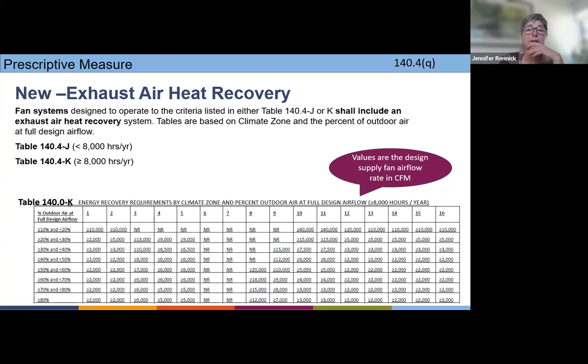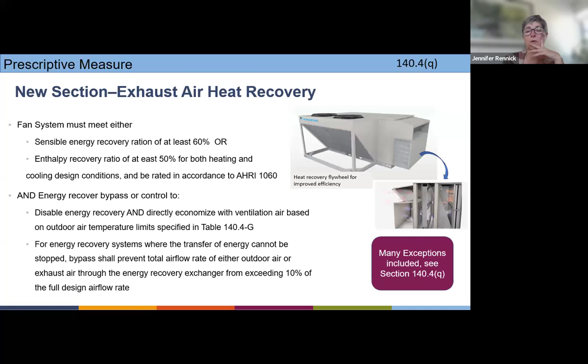And then a lot of the bigger systems we're seeing, they'll just have a large air handler that has a heat recovery flywheel that is going to bring in the outside air to a system that has a lot of ducts. And now for these systems specifically, there's requirements about their enthalpy recovery ratio being at least 50% for both heating and cooling, for example, and the sensible energy recovery ratio of at least 60%. And then certain things we need to know on bypass controls, and there are exceptions, but we're just seeing some of the larger commercial projects have pieces of equipment like this on the roof to bring in that outside air. So those sections were rewritten.